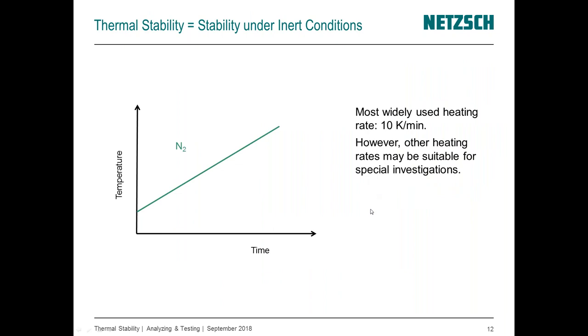Thermal stability is usually investigated with common measurement parameters: 10 K/min is a very common heating rate, and gas flow rate is usually kept constant at 20–40 mL/min. However, the heating rate can change and will influence results, so when comparing measurements, always verify that conditions are identical. Changing heating rates is a common technique especially for kinetic evaluation, where the time-temperature correlation is obtained by running three to five tests with different heating rates.